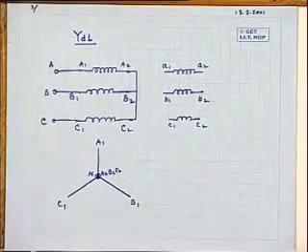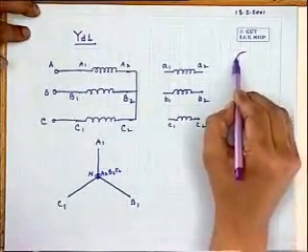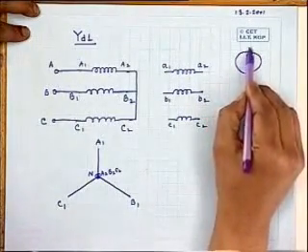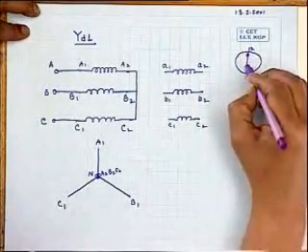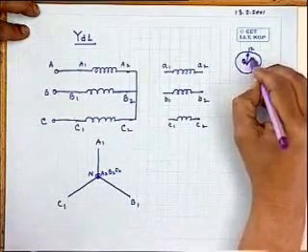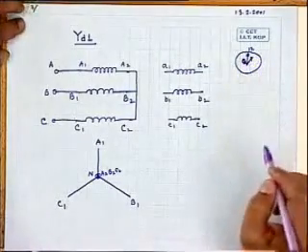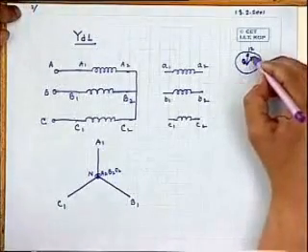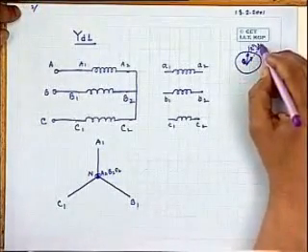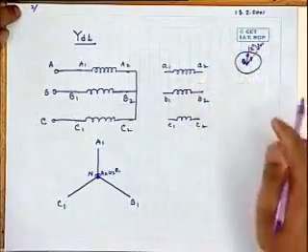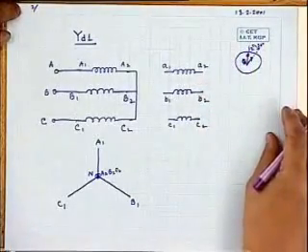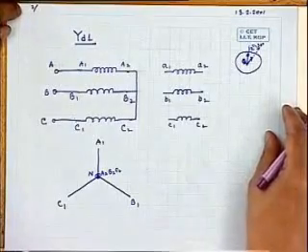Now this one means, in the clock convention, I want to get this one. That is, the primary side voltage at 12 and your secondary corresponding phase voltage, one means here, it will be here. And the angle between these two divisions, as we know, in a clock between two consecutive numbers is 30 degree. So this is a 30 degree lag connection. Okay.